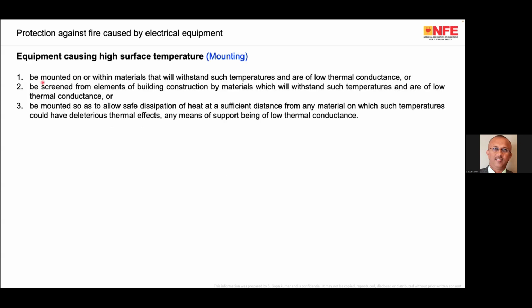Now, what do we do? If you know the thermal characteristics of the equipment, the first step is to mount the equipment in such a way that the temperature produced by the equipment during normal operation is not harmful to the nearby equipment or the nearby environment, because each electrical apparatus produces heat during its normal operation. The only point is that the amount of heat may be very little in one product and more in another, and due to aging the thermal effect may increase. From the manufacturer's guidance, technically you are supposed to get this information. So you have to mount the devices in such a way that the thermal effect is not harmful to the equipment.